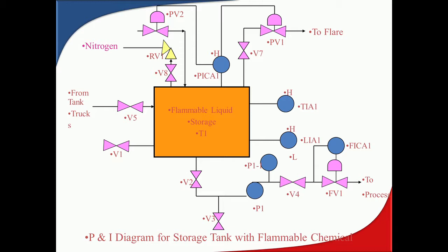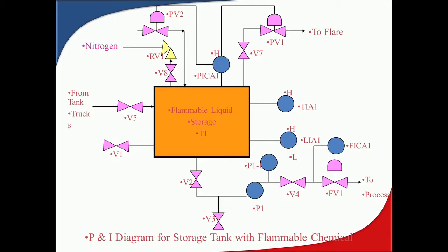Then, so pressure may rise. No, for now pressure is a different parameter. Now we are talking about the level in this. What can be the causes of level in this? Till now we have talked about 4 or 5 causes. Anything else? If this is open, V2 will be completely open. If by chance this V3 is kept open without knowing, this will be kept open. Okay, so this is in terms of level.